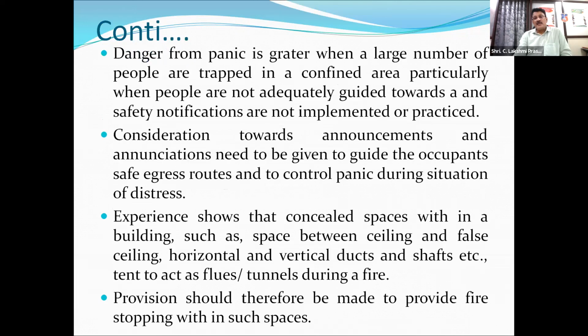So the important things are that the exit should be protected from all these effects of fire like smoke and fumes, and it should be visible. There should be proper directions. There should be clear lighting, because in a fire there is the problem of the electricity being disconnected from the main source. So there should be an alternative source, from battery backup and also a generator, for various fire safety related equipment, including the signages and lighting of the exit route, the egress path.